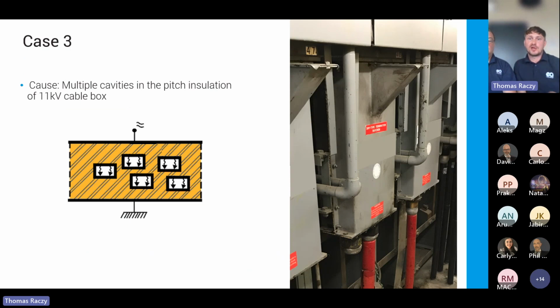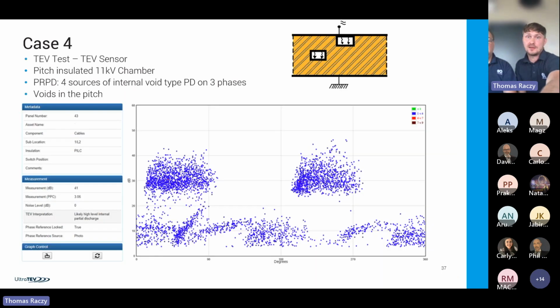And those discharges, all of those were detected in 11 kV pitch-filled insulation. Sometimes over time, this pitch could shift a little bit, creating gaps and voids, hence the discharges. Next case study is from TEV, with a TEV sensor as well. So, indication of internal discharge.